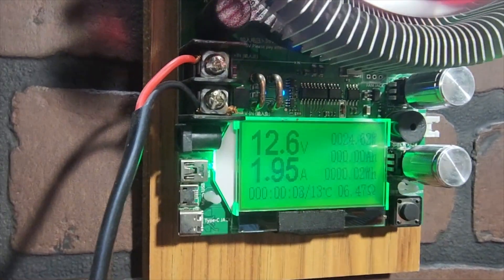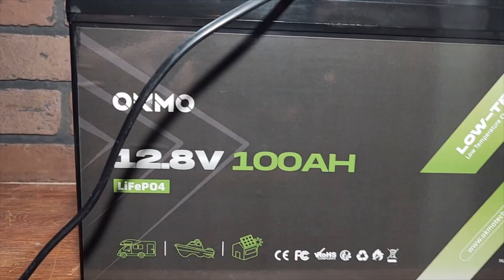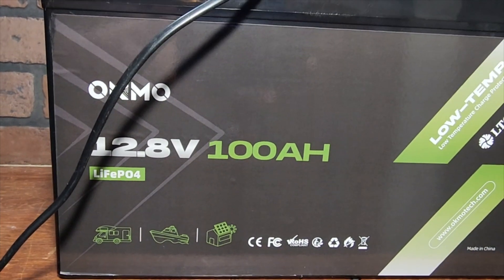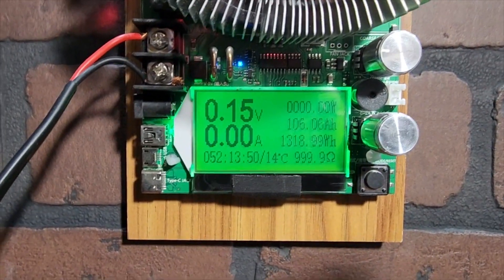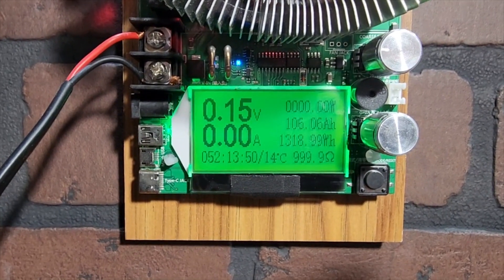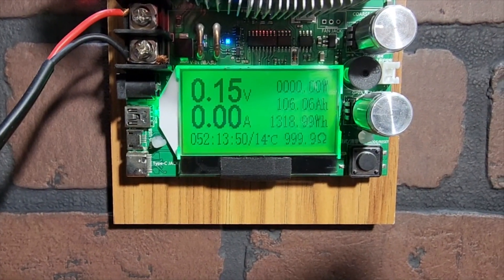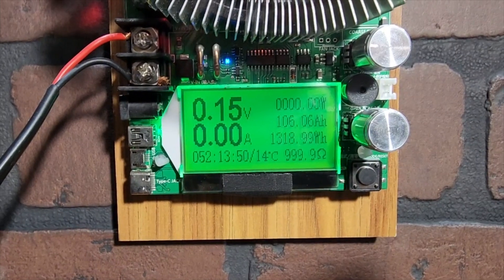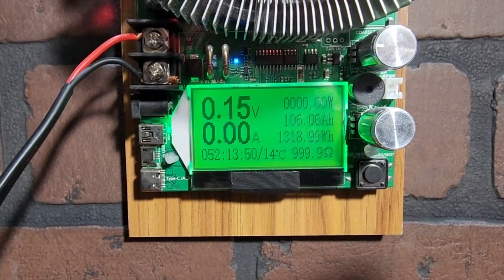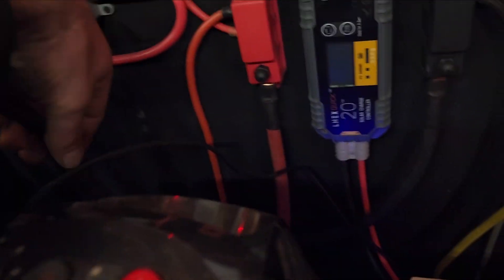The capacity tester will run until there's absolutely no current left. You can see we're at 12.6 volts, adjusted to just under two amps of power draw. We're supposed to get 100 amp hours out of this battery. After letting it run for 52 hours, we actually came up with 106.06 amp hours and 1,318.99 watt hours — it outperformed its rated capacity, which is great.